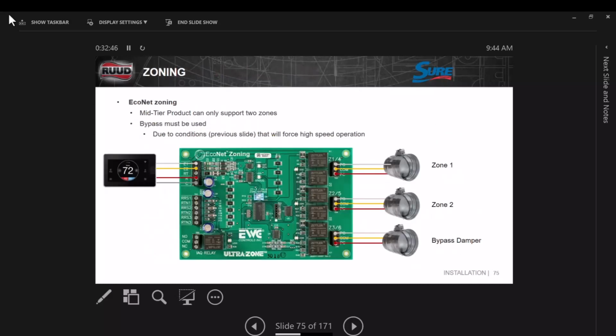So whenever we're doing zoning, do any of you do zoning? Some. With the mid-tier stuff, we're allowed 2 zones and a bypass. Now on the full EcoNet high SEER stuff like 18, 20s, those you can run multiple zones on them. But just be cautious how you do it. You know, we don't want to zone just the master bedroom because they want to keep it at 68 degrees at night. Because we all know that that's going to be the only zone called on, and that duct's not going to be big enough unless you put enough duct in there. You know, so just be careful.